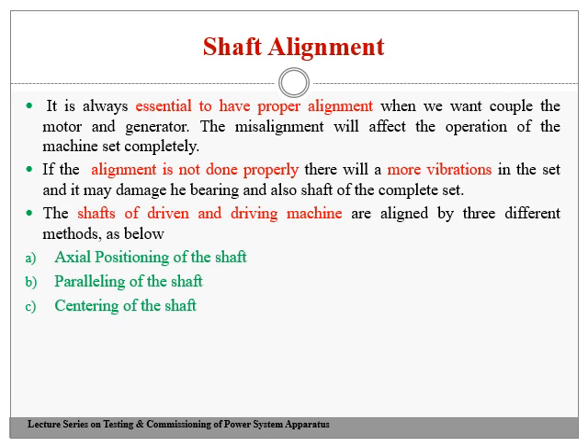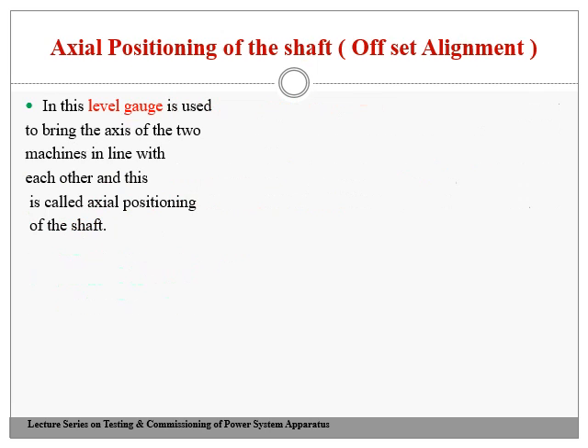First, you have to do the axial positioning, then the paralleling of the shaft, and the last method is the centering of the shaft. If you do all three, then we say that both the driven and the driving machines are properly aligned, and then you can have the proper coupling. If you have not done any of these three methods, the alignment may not be proper, and unwanted vibrations come into the picture, which will hamper the operation of the induction motor by damaging the bearing as well as the shafts. We'll see them one by one.